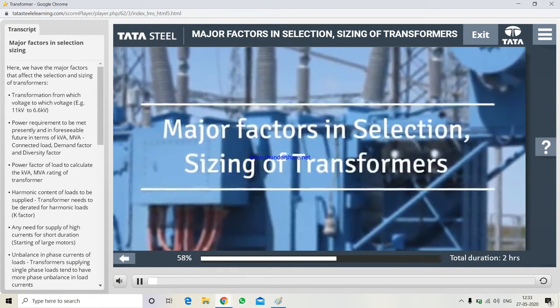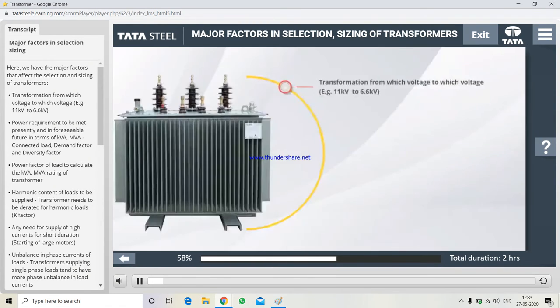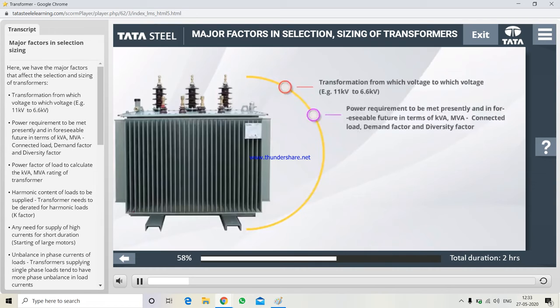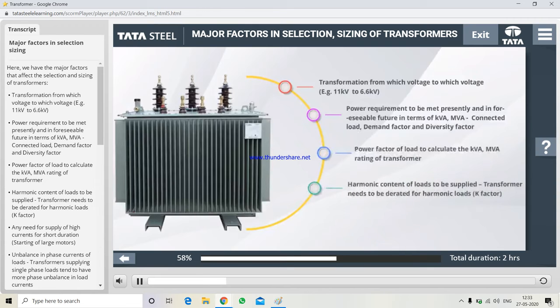Here, we have the major factors that affect the selection and sizing of transformers. Transformation from which voltage to which voltage, example 11 kV to 6.6 kV. Power requirement to be met presently and in foreseeable future in terms of kVA, MVA, connected load, demand factor and diversity factor. Power factor of load to calculate the kVA, MVA rating of transformer. Harmonic content of loads to be supplied. Transformer needs to be derated for harmonic loads, K factor.